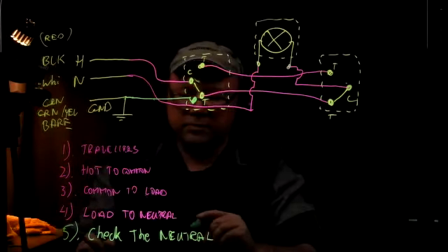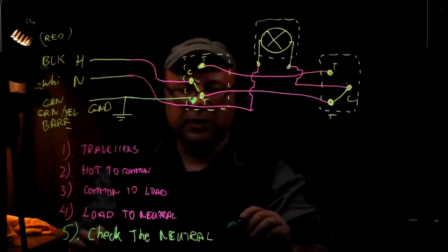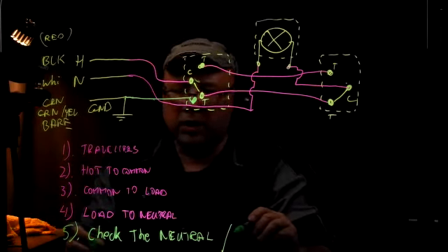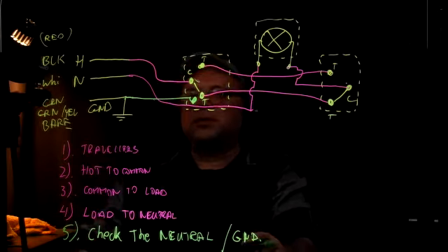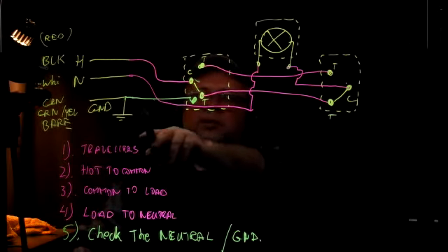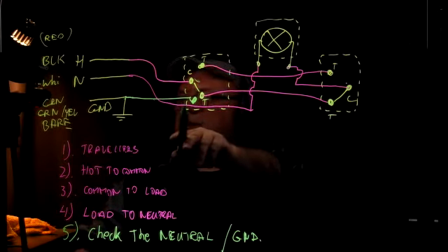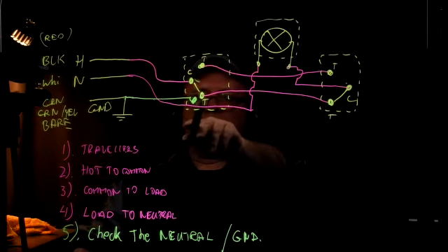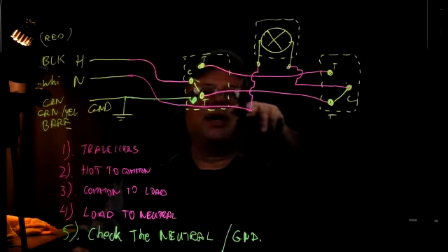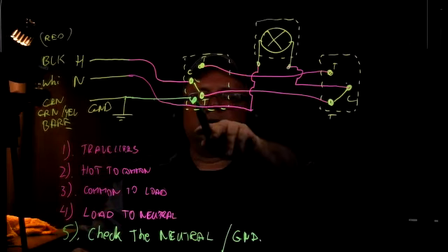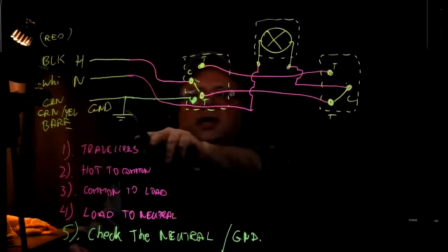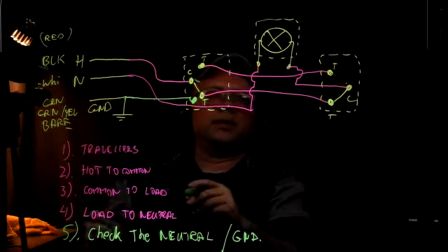Neutral, and of course the grounding as well. If it's a PVC, if it's an EMT raceway, you just have to connect the bonding wire right to the first box. And if it continues to be a metallic tubing, then it's okay. Just now, if it's a PVC, then you still have to run another wire, right?